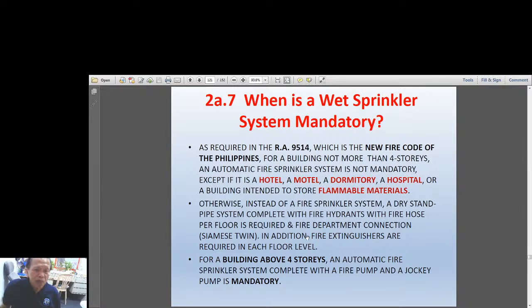Okay? Otherwise, there is another requirement. If flammable materials are stored in that building, even if it is 1 story, 2 story, 3 story, less than 15 meters, if there are flammable materials stored, then you must provide a sprinkler, an automatic sprinkler system. Okay? Otherwise, it's possible not to use a sprinkler system.